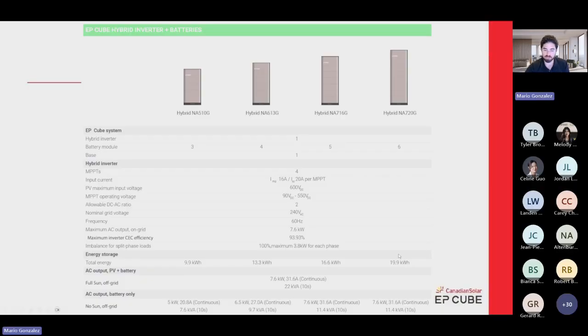The kVA for the system is 22 kVA for 10 seconds. This is important when you're sizing for AC equipment and whatnot. However, I do recommend installing soft starters on the big loads, like AC equipment, pool pumps, and such, just because you never know when you're going to lose power, and you're never going to have the battery at full capacity if you lose power. And if you have a small system, like the battery module, I will always recommend installing a soft starter on the AC.